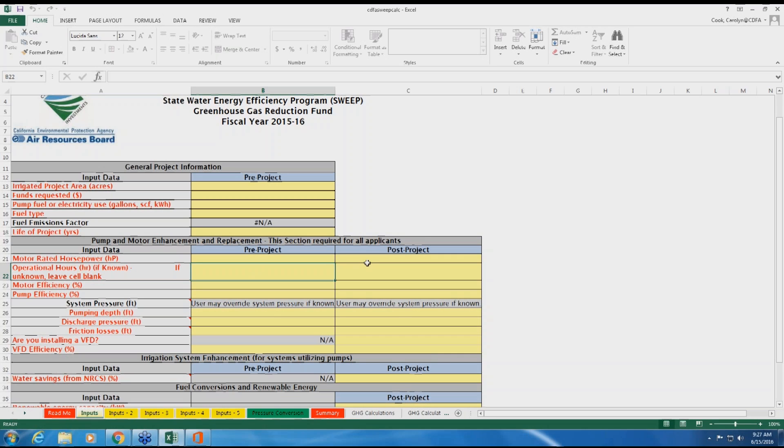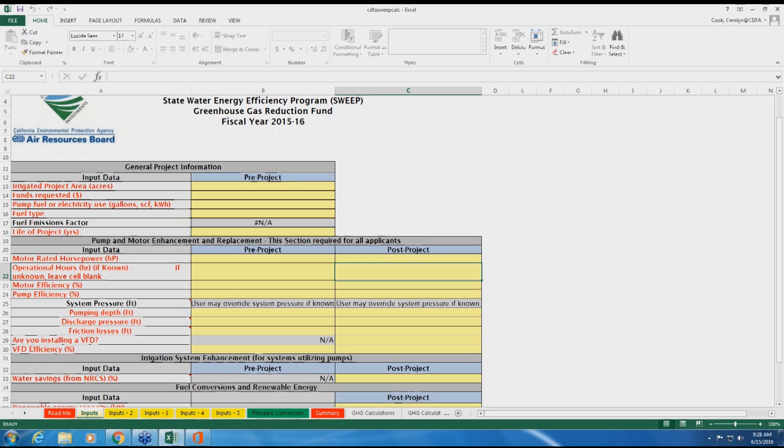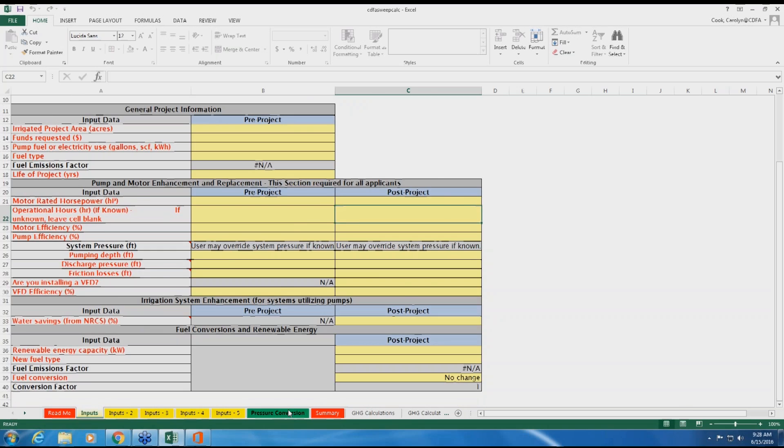In the right-hand column, for post-project data, it should be the expected performance of the pump after the project has been implemented. If you are not making adjustments to the pump, this information will remain the same. If you are replacing with a new pump or motor, please enter the information from the manufacturer in this column. When entering information about system pressure, if the data you have is in PSI and you need to convert to feet of head, please select the green pressure conversion tab to perform a simple conversion equation to calculate pressures in feet.